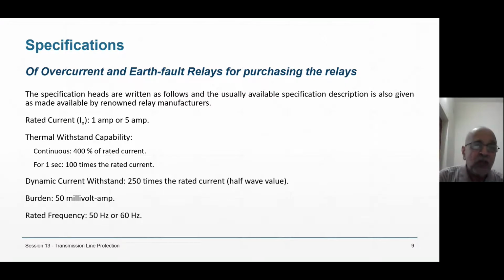You will first ask for rated current, 1 ampere or 5 ampere. Some relay manufacturers give 1 ampere or 5 ampere, and some give both 1 ampere and 5 ampere. Whatever you want to use, you can use. Thermal withstand capacity: continuous thermal withstand capacity of all numerical relays is 400% of rated current. That means if its rating is 1 ampere, it can withstand 4 ampere for 365 days, 24 hours. But for 1 second, it can withstand 100 times, that means 100 ampere for 1 second.